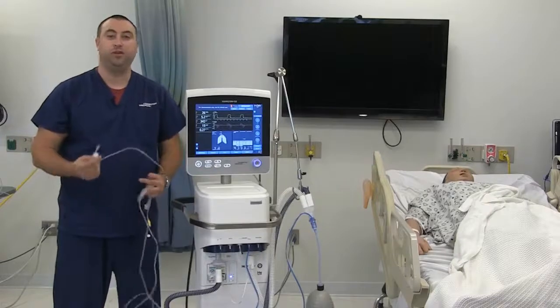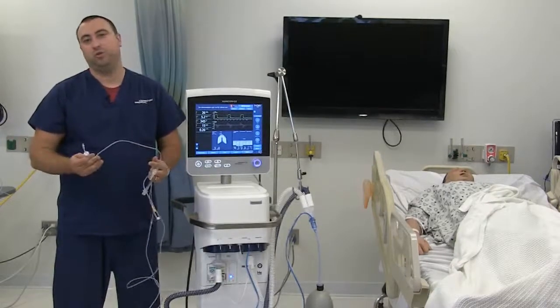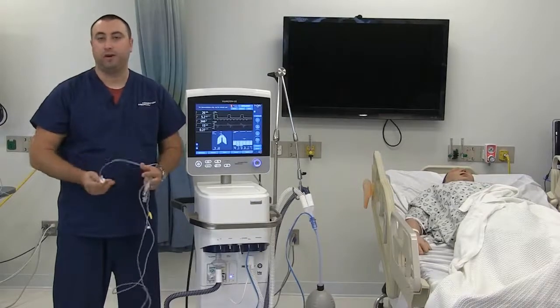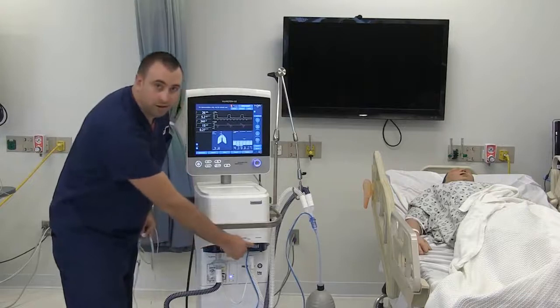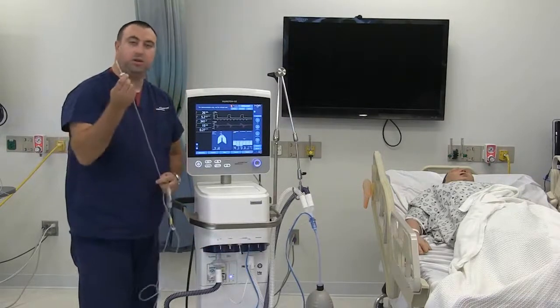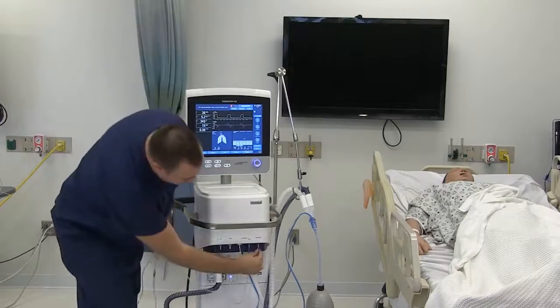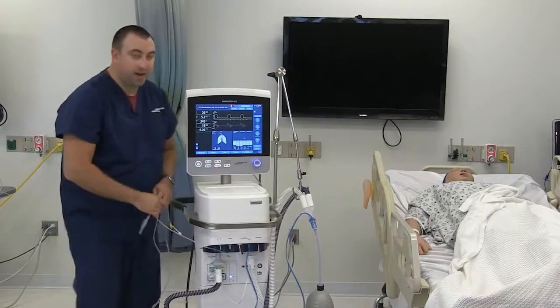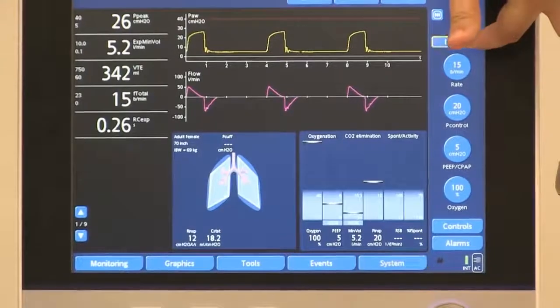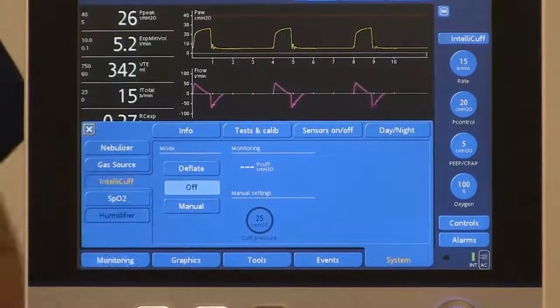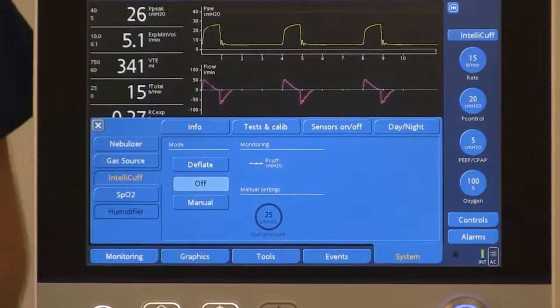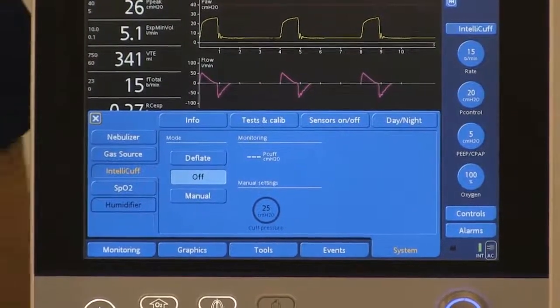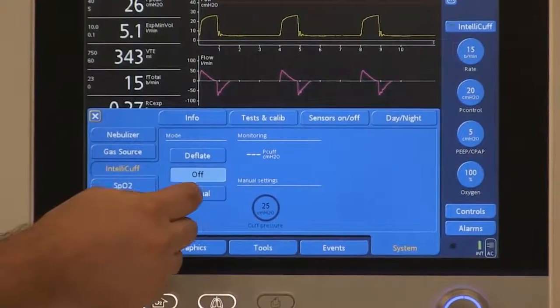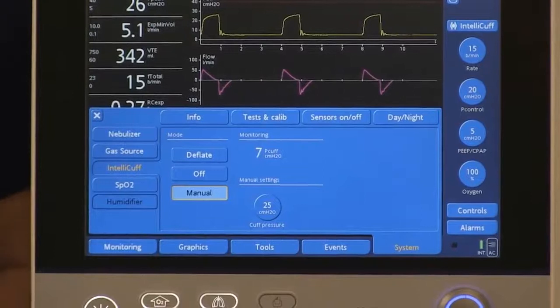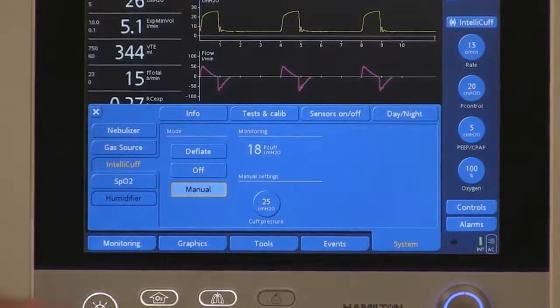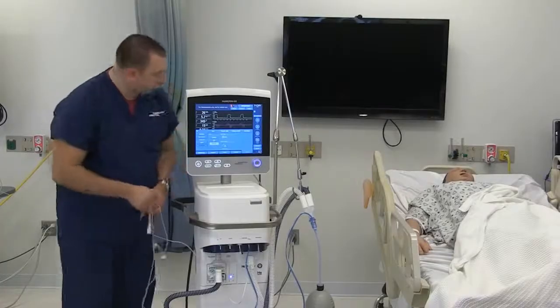IntelliCuff is a unique feature to Hamilton Medical, which allows the user to maintain and monitor your cuff pressure. You'll find the IntelliCuff port, and you will hook in your IntelliCuff tubing, filter line at the port there. And then you can access IntelliCuff on your user interface by hitting the IntelliCuff tab, and that will bring up your IntelliCuff menu. When IntelliCuff is in the off position, it simply monitors cuff pressure. By hitting manual, you can actually set the cuff pressure that you would like it to maintain. Right now I have it set at 25, so we'll leave it there.